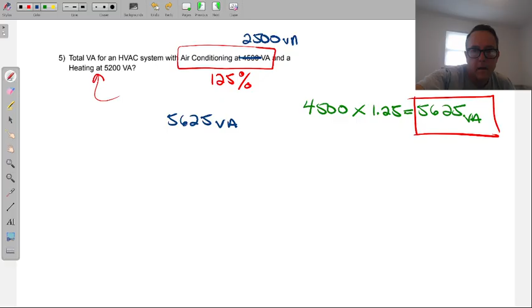And again, this is a bit of a confusing code. They're going to be on the same breaker? They're always on. This is what we're saying. We're saying that this system is a non-coincidental load. That means the HVAC systems are both on the same breaker: the heater inside the unit and the air conditioner inside the one unit. It's one unit outside the house. Inside it'll have the heating system, and inside it'll have the cooling system. So the air conditioning is also going to come first for the VA times the 1.25? Depends which is bigger. If it becomes larger, then yes.